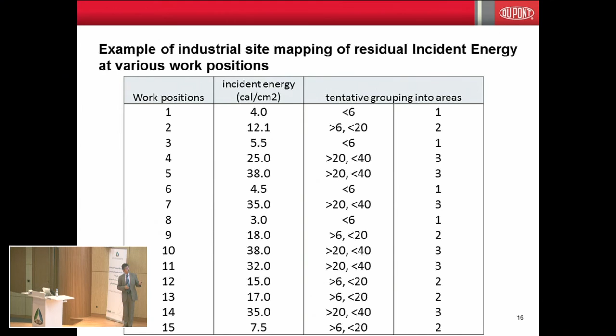This is, today, what is important to understand. The first stage, as we said, is trying to protect from the heat. So today, as you're looking for arc protective clothing, before you evaluate the arc protecting capability of a clothing, you need to validate that the clothing is also fire resistant. Why? Because fire resistant clothing is generally heat resistant. And for that, the base is to look at ISO 11612.